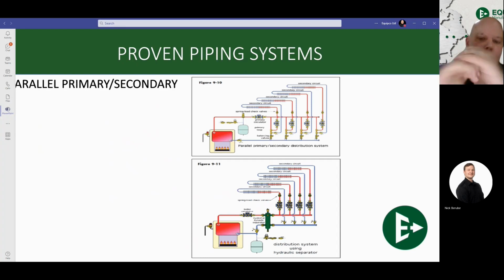And that leads us now into the bottom right-hand picture that I want you to take note of here. This is your modern hydronic system. Your primary loop from your boiler to your low-loss header and back, and then your system going out and zoned with either pumps or circulators, doesn't matter which. This is a true modern system where we have our high-efficiency air, dirt separator, magnetic separation, all of our pieces in one, easy to zone. All of our zones see the same temperature, designed for each individual zone to work. This is a proper modern hydronic system. This is the one that you want to see day to day, all day, every day.